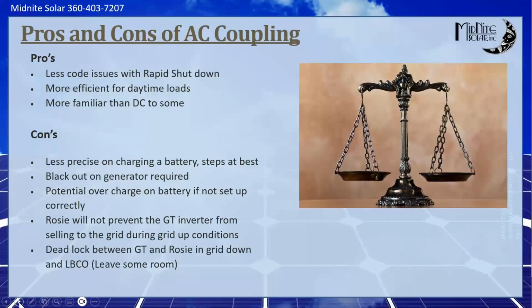So for the purpose of this pros and cons, some of these are generic, some of them specific to the Rosie. But we're going to talk about some of the pros and cons and why you may or may not want to do AC coupled. Some of the pros, it's less code headaches. It's easier to install, right? It's much easier to go ahead and put Enphase inverters on the roof and run 120/240 down, and you don't have your rapid shutdown requirements. You don't have all the DC cabling and conduit requirements. It's a more easy install, simpler to use type thing. So that is one benefit of AC coupled, it can get you around some issues with permitting and inspectors and complexity of install.